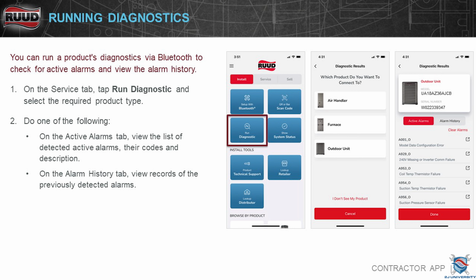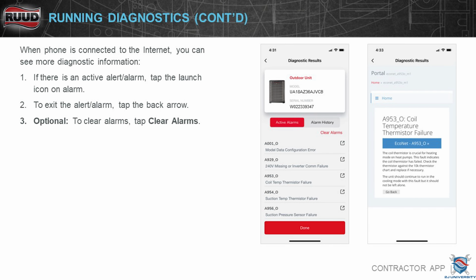And if you're selling, say, a TH8321 versus an Econet, there's not that much cost difference, and you're going to get way better functionality out of the Econet. Once again, your diagnostic, you can go through, it'll show you active alarms, alarm history. You can also clear out any alarms in here once you've fixed the unit. You can go in and clear those out of the alarm history.